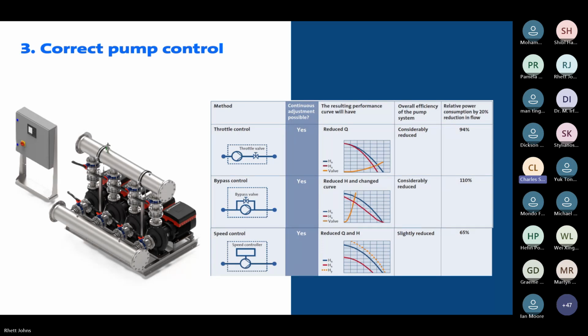And then you go down to bypass control. So this is when we recirculate flow when it's not required. Again, two issues we have with this method. The first is the unnecessary consumption of power when it's not required. As I said, the pump is still continuing to run at those conditions. In fact, if you go back to the motor example that Rhett gave, when we have a standard motor running at 100%, these first two are examples of where that's happening. And then in a bypass situation, secondly, is the unnecessary heat that's being added to the system through recirculation.